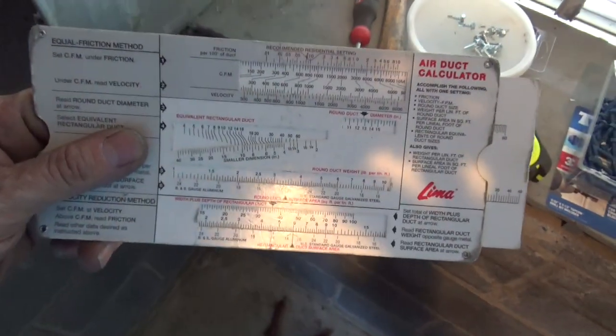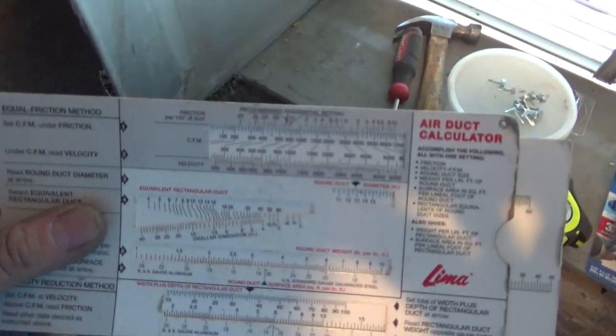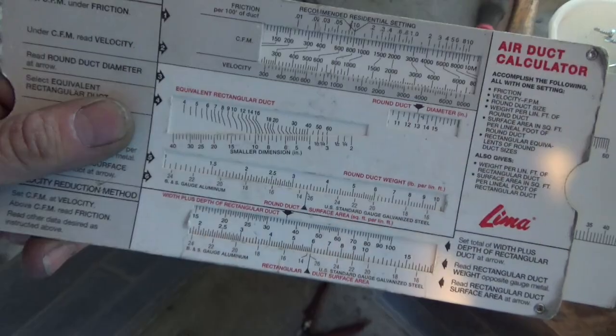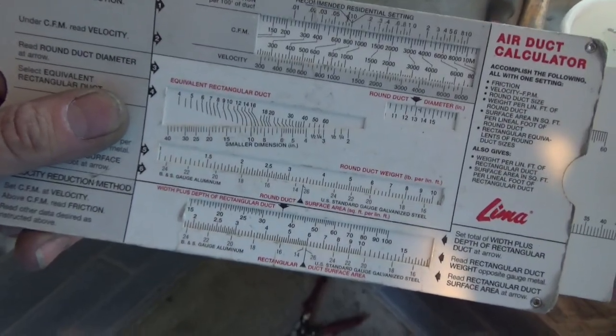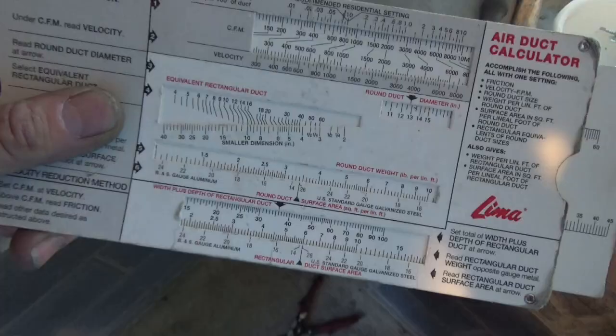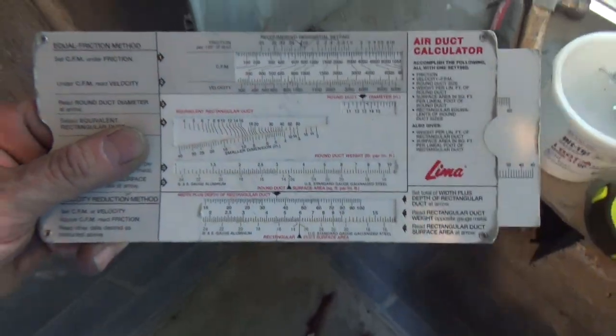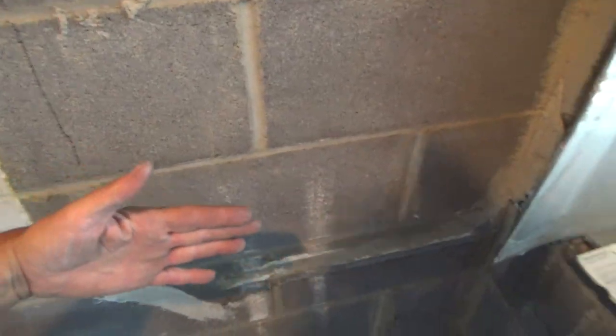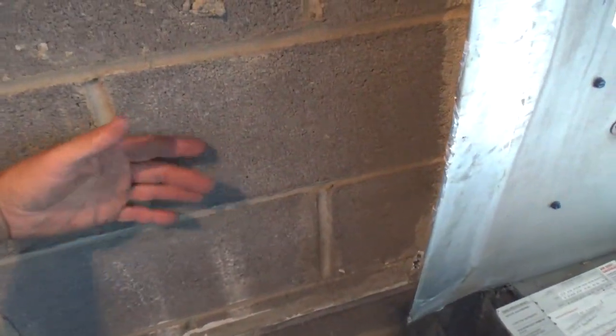Now most of the units out here would be a 2-ton, which would be 800 CFM, 5.5 by 28, or if you got 6-inch, 6-inch by 24, and that's kind of what they had. Well, yeah, closer to 6, but they didn't insulate the wall. So I'm going to open up this brick right here. It's called a dry diamond blade. Real easy.